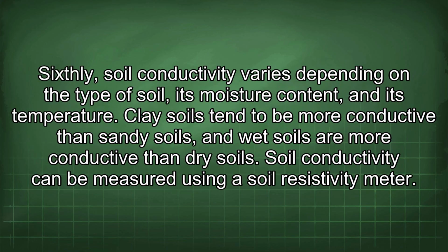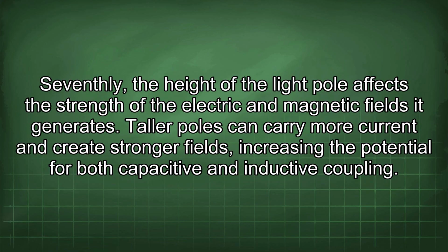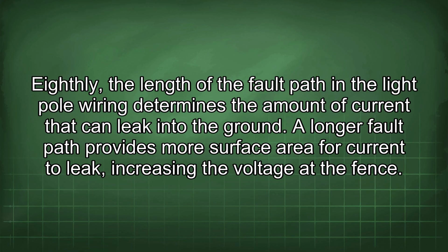Sixthly, soil conductivity varies depending on the type of soil, its moisture content, and its temperature. Clay soils tend to be more conductive than sandy soils, and wet soils are more conductive than dry soils. Soil conductivity can be measured using a soil resistivity meter. Seventhly, the height of the light pole affects the strength of the electric and magnetic fields it generates. Taller poles can carry more current and create stronger fields, increasing the potential for both capacitive and inductive coupling. Eighthly, the length of the fault path in the light pole wiring determines the amount of current that can leak into the ground. A longer fault path provides more surface area for current to leak, increasing the voltage at the fence.